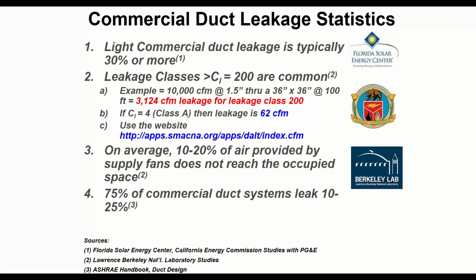Puns all intended. Duct leakage is horrible, both residentially and commercially. It is completely normal for ducts to leak 20, 30, 35%, and nobody even bats an eye. It's just kind of accepted that air is going to be leaking all over the place. But when it leaks in walls and shafts and building cavities and above the ceiling grid, that's warm air or cold air that was not delivered to the actual space, which means your system has to run more to get the air you need into the space. So we're going to seal all this stuff up and obviously save a boatload of energy in the process.